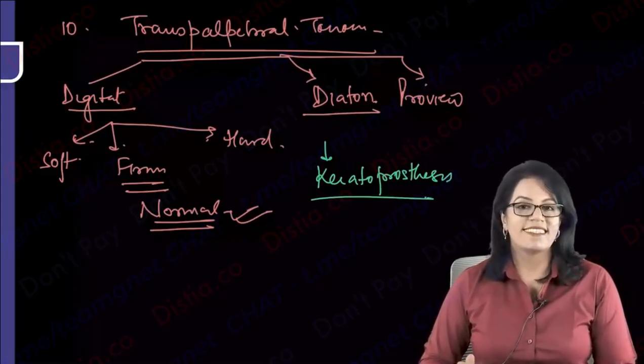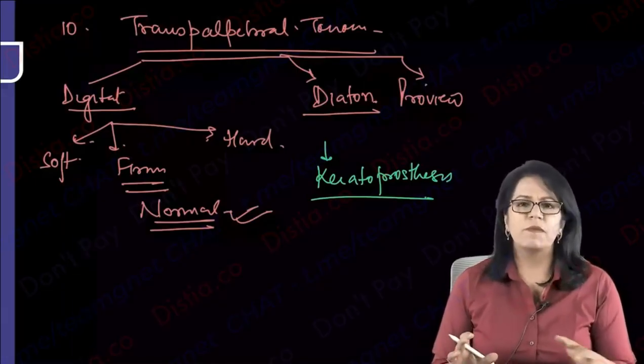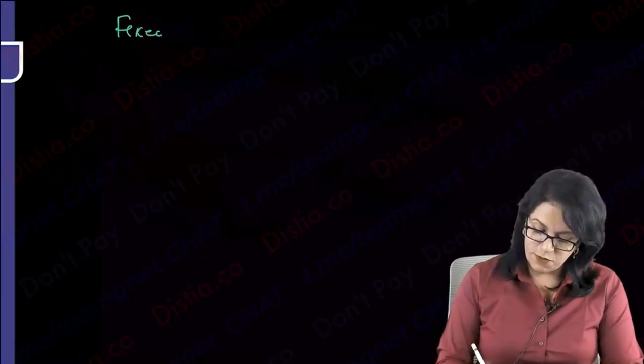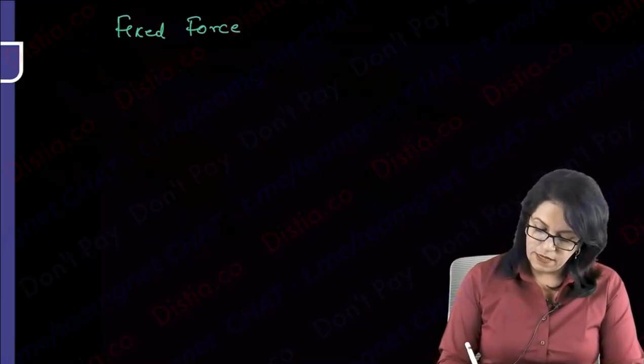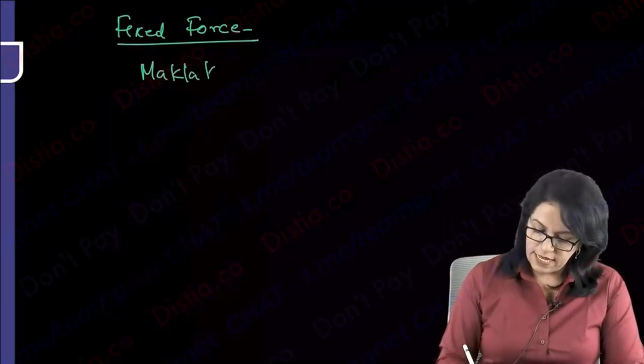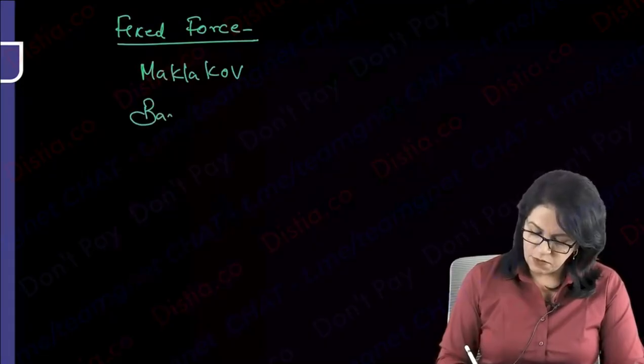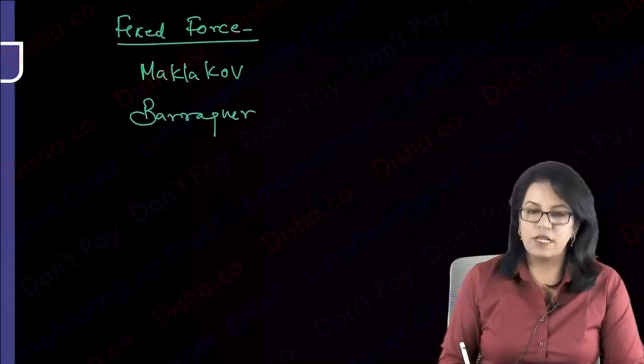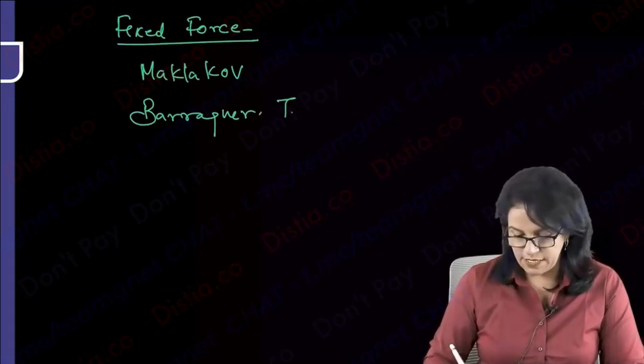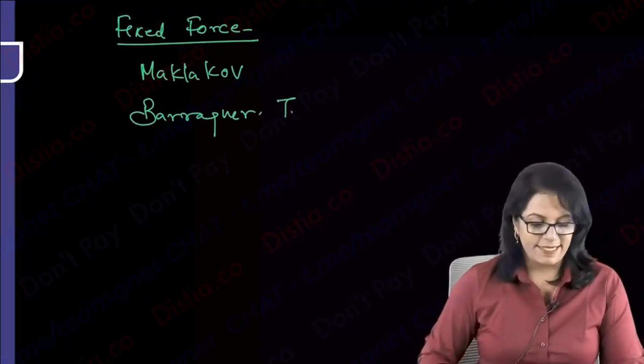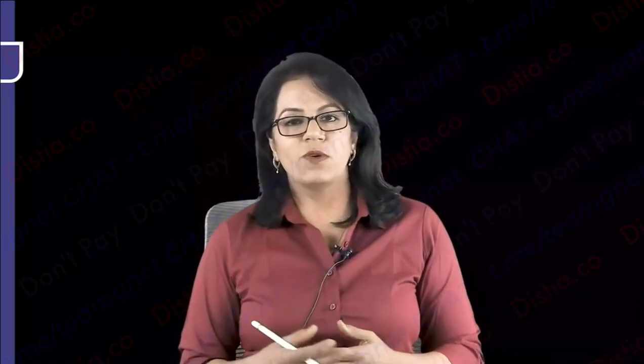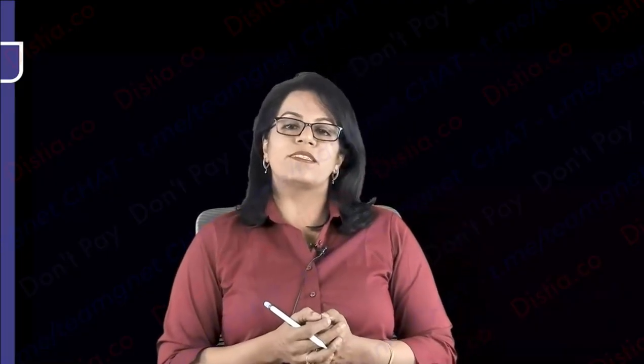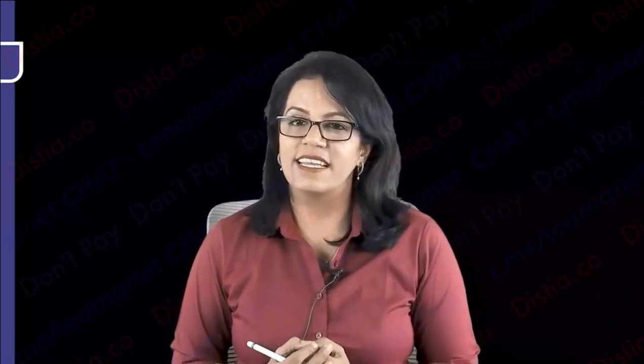Once we know this, we come to the next important thing. These were all variable force. Now just be familiar with fixed force also. Write down what the fixed force tonometers are. I would like you to just know the names: one is Maklakov and one is Barraquer. Barraquer is generally used before LASIK surgery also. Do you realize even the gold standard is also not reliable? Goldmann, which I am talking about, depends on the central corneal thickness.